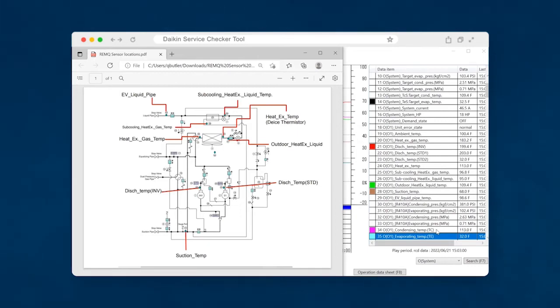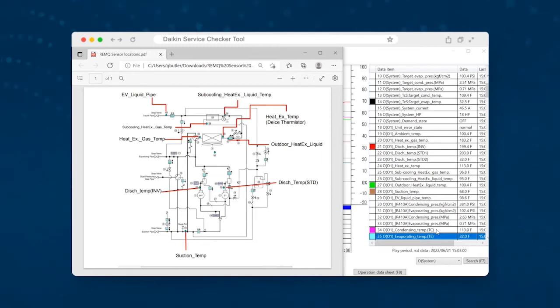So the range for our suction superheat is supposed to be five and a half degrees to 14 and a half degrees. And so right off the rip, we see now the compressors appear to be starved of cooling effect from the refrigerant. And so now we're already starting to come to a conclusion, okay, this system is low.